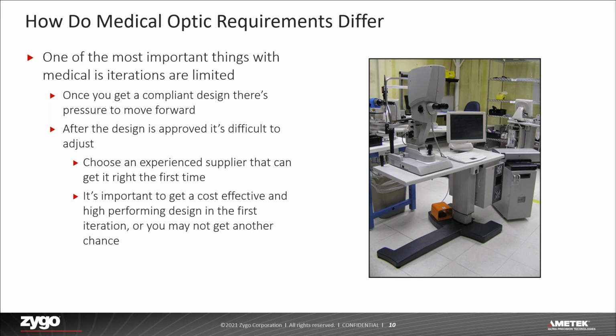When you start to develop an optical system in the medical field, one of the most important things you should know early on is that you won't get many chances to iterate through the design. In many cases, once the optical system is approved, you're pushed to deliver a product. Once you receive approvals, both within your own company and from the government, that design is effectively fixed in place. Going back and trying to change any aspect of the design may be extremely difficult. With that in mind, you need to make sure the design will meet your requirements upfront and shouldn't need to change.